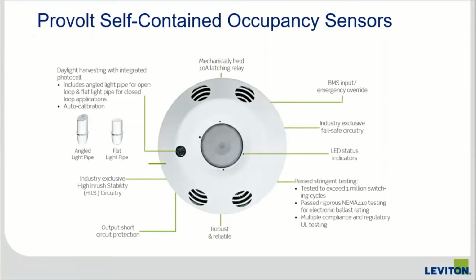And one other important feature is that it has industrial exclusive fail-safe circuitry. When I say fail-safe circuitry, in any unforeseen circumstances or accident, for example if there is a fire accident and the sensor fails, it will not let the relay stay off. It turns on the relay automatically so that the lights are always on. So this is a very life-saving feature that the sensor has. Apart from that, it has a BMS input or emergency input, which can be connected to a fire alarm or BMS, and you have a manual override as well.